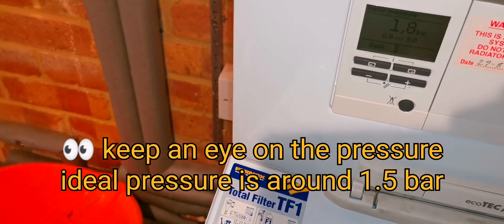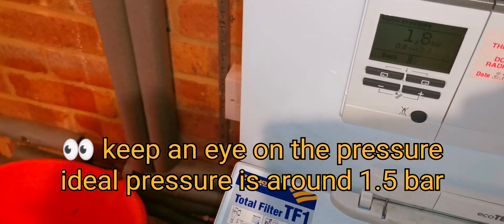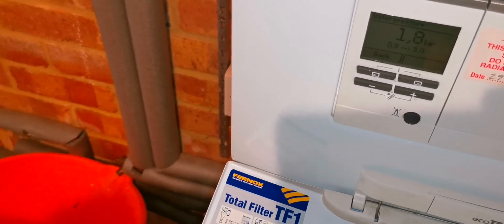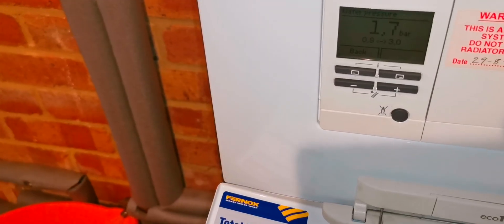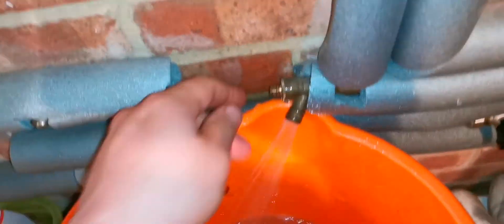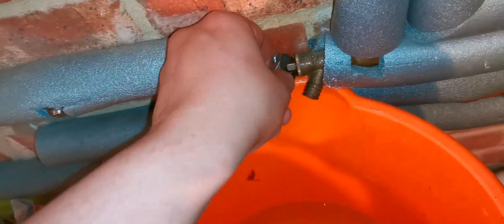You might have a separate pressure gauge you want to keep an eye on. You don't want it going below one bar, but ideally you want it around 1.5 bars or in the green if you have a gauge.